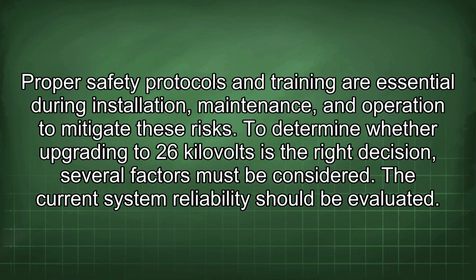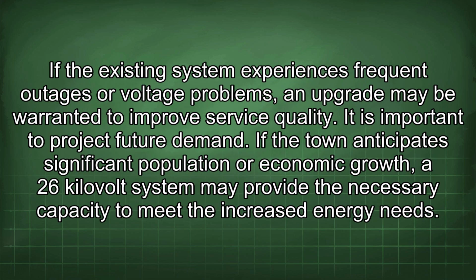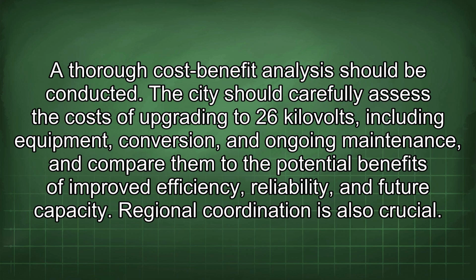To determine whether upgrading to 26 kilovolts is the right decision, several factors must be considered. The current system reliability should be evaluated. If the existing system experiences frequent outages or voltage problems, an upgrade may be warranted to improve service quality. It is important to project future demand. If the town anticipates significant population or economic growth, a 26 kilovolt system may provide the necessary capacity to meet the increased energy needs. A thorough cost-benefit analysis should be conducted. The city should carefully assess the cost of upgrading to 26 kilovolts, including equipment, conversion, and ongoing maintenance, and compare them to the potential benefits of improved efficiency, reliability, and future capacity.